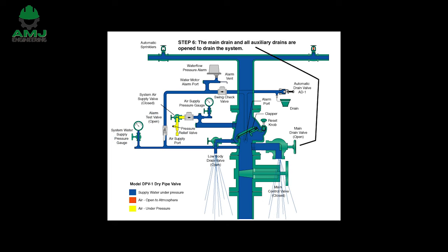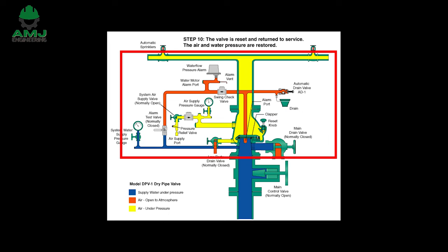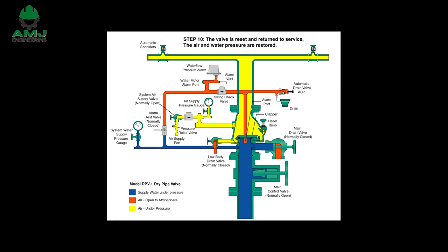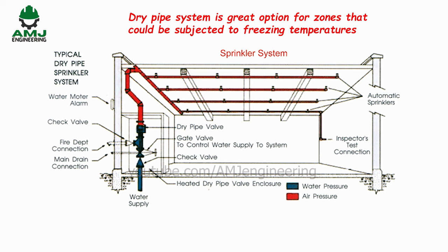Since there is a delay between sprinkler operation and water flow, the size of dry pipe systems is limited. This size limitation is intended to minimize the amount of time water delivery is delayed. A dry pipe system is a great option for unconditioned spaces or locations where the temperature cannot be guaranteed to be high enough to prevent water in the system from freezing.